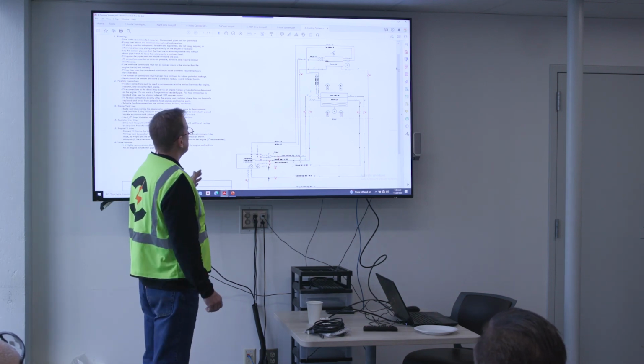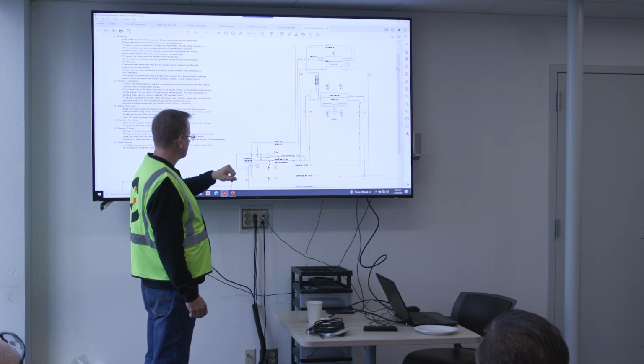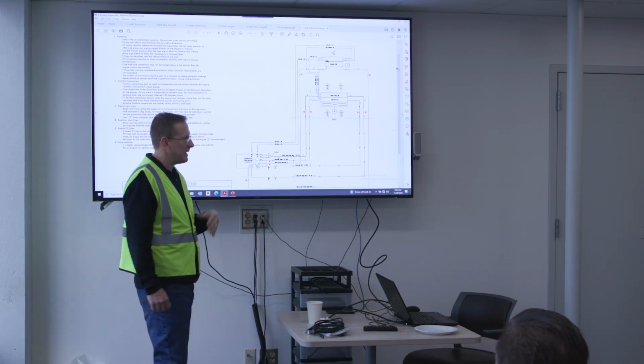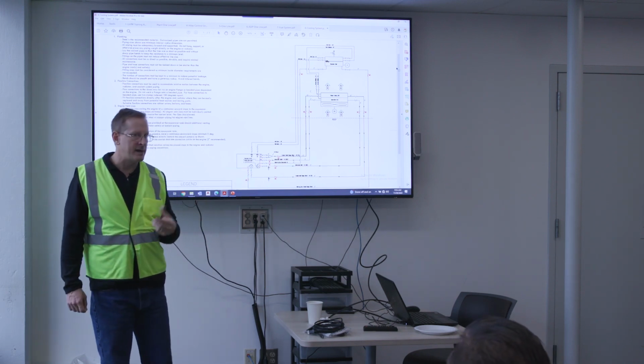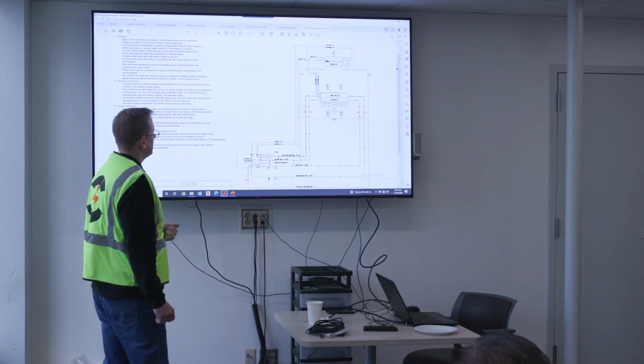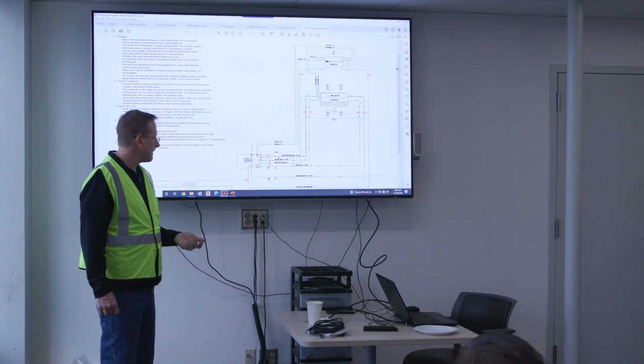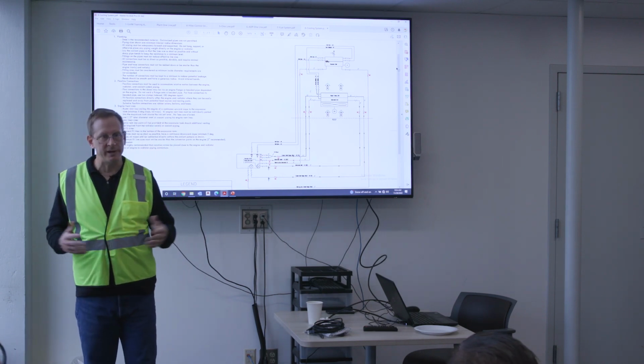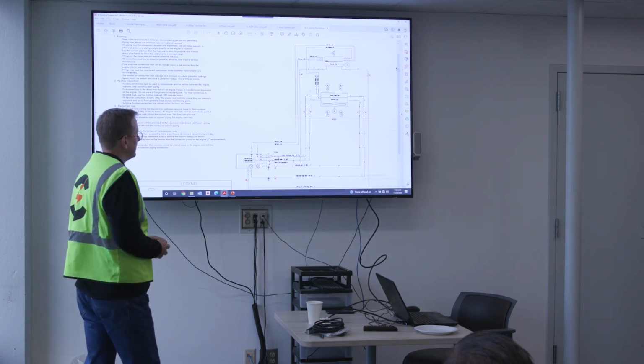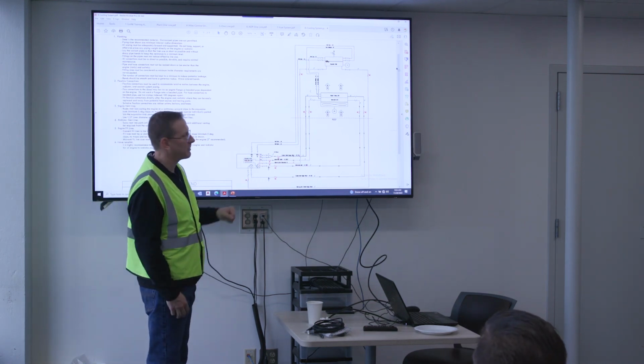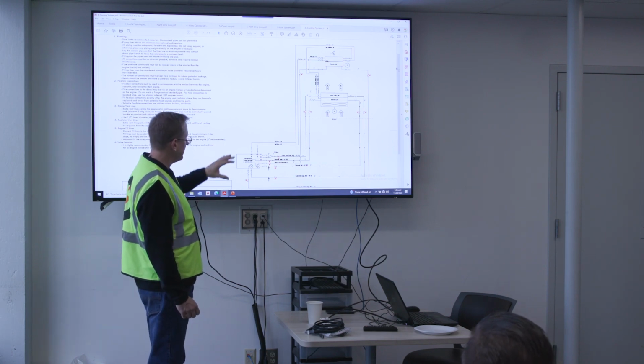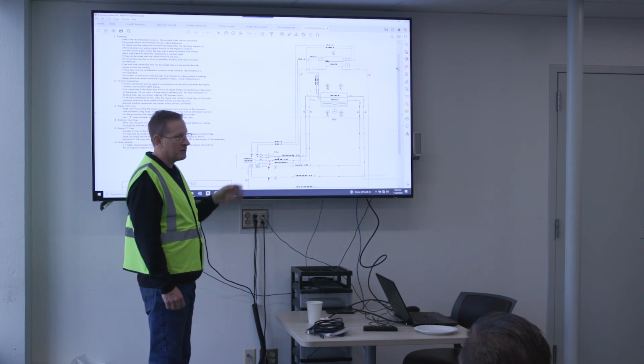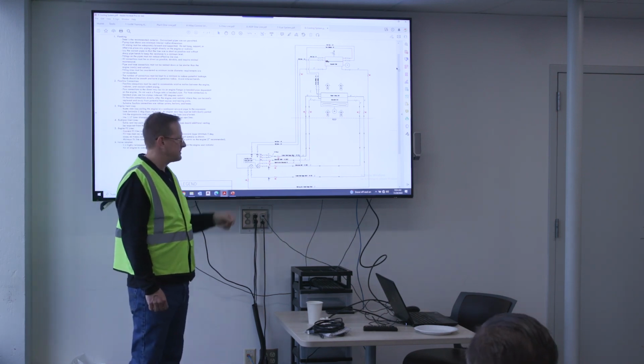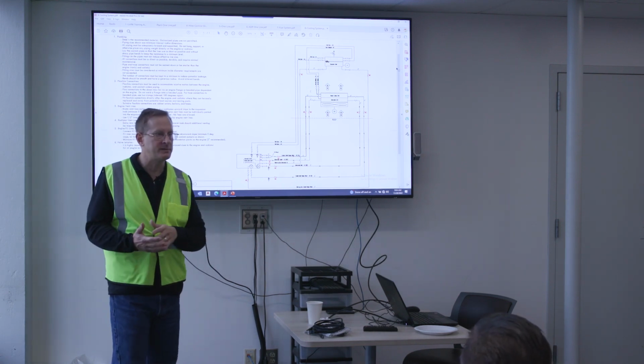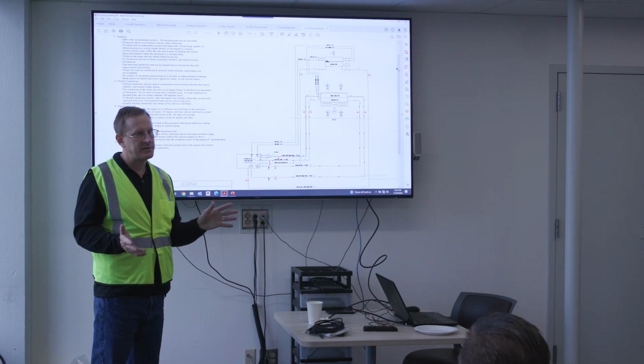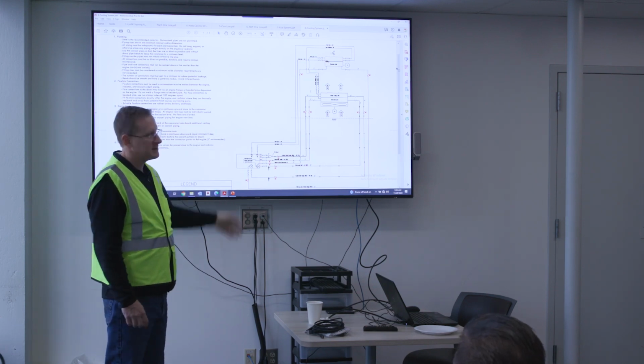for whatever reason. And then of course there are a number of isolation valves between the engine and the radiator, both at the radiator and near the engine as well, for isolation for whatever reason. Okay, it's actually nice to have those, because if you have to, let's say, replace a water pump or something on the engine, you don't have to drain the whole entire system. You can just close the valve and just drain part of the system in order to conduct whatever repair that would be. But again, a very simple system. It's a one-speed fan. It's either on or off, and the engine itself will actually regulate its own temperature with its thermostats. So it'll open the thermostats as much as it needs to regulate its own temperature, but the fan runs at one speed, and again, is controlled by the Hitec PLC.